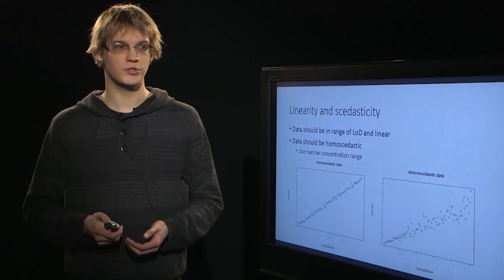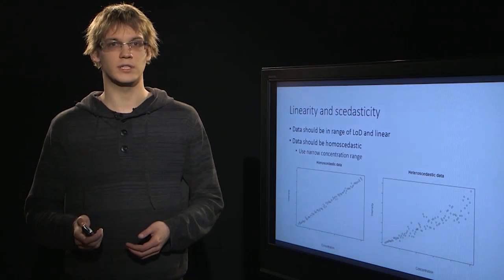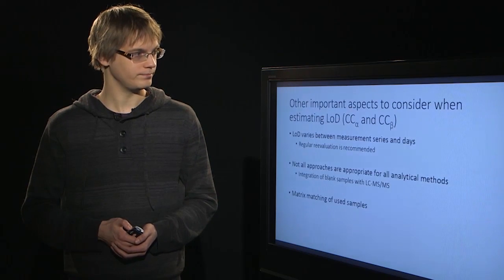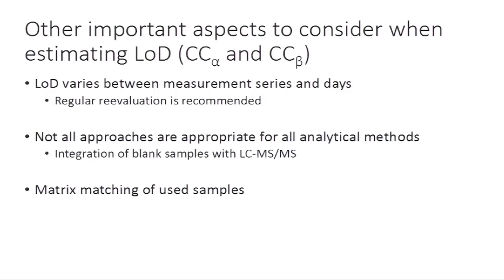Other approaches for estimating whether the data is heteroscedastic can be found in the materials of the course. Some other important aspects to be aware of: limit of detection varies between measurement series and also between days. So a regular re-evaluation of limit of detection, and also decision limit and detection capability, is highly recommended.